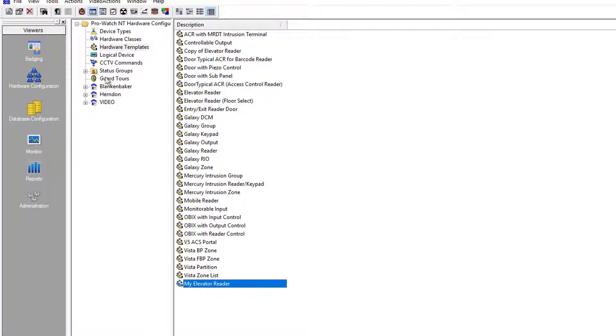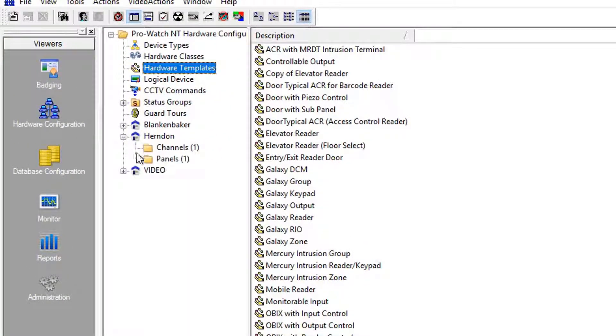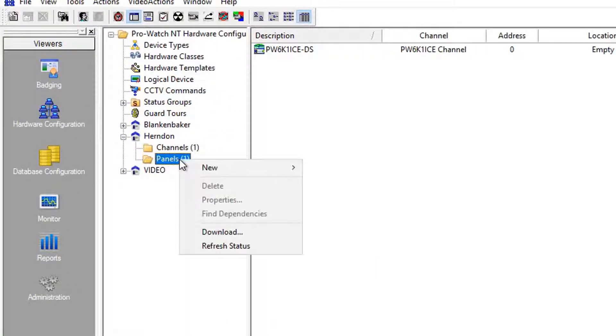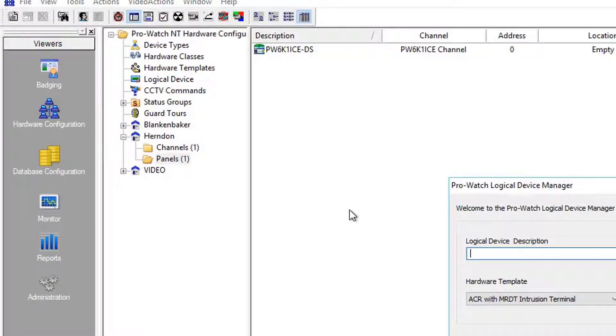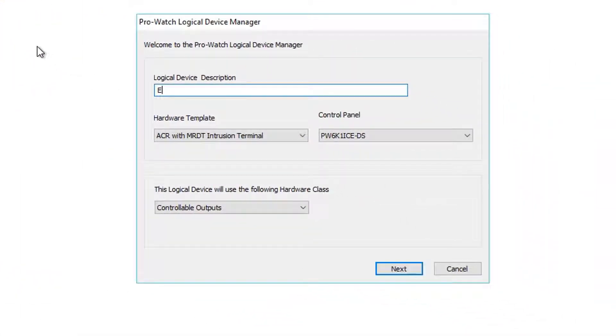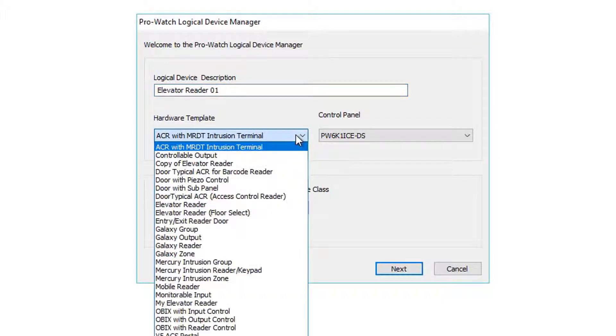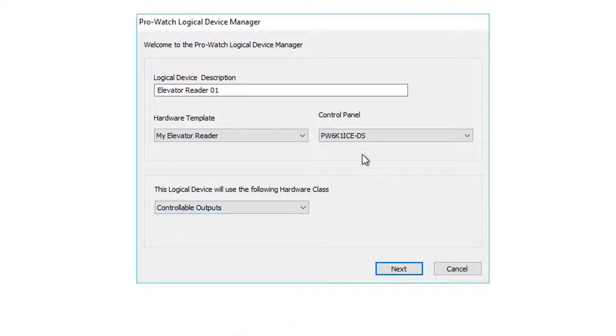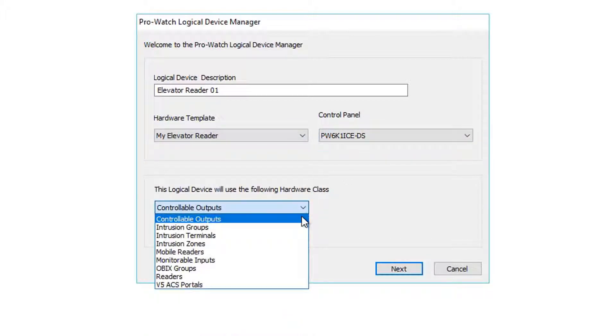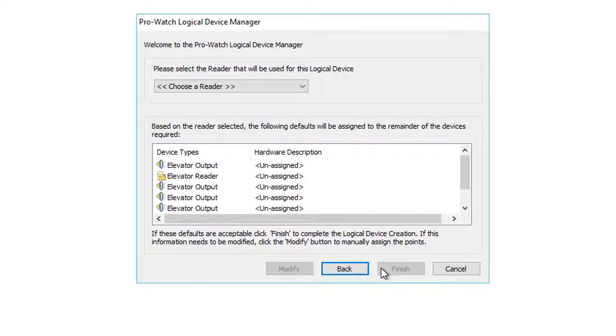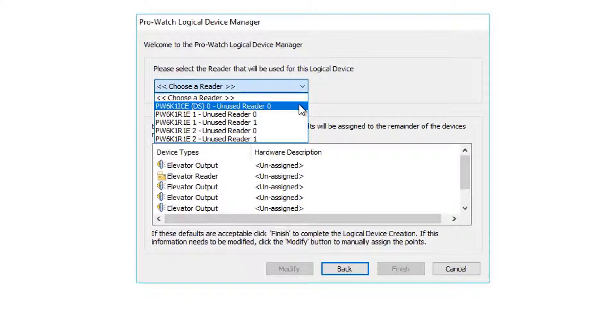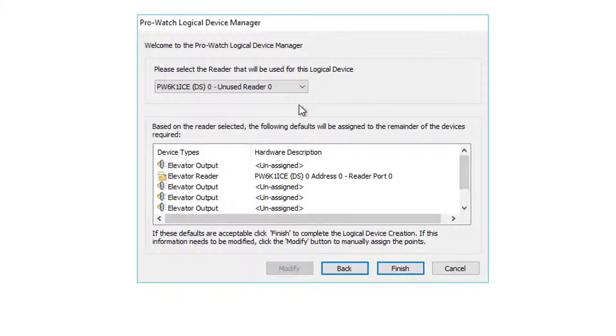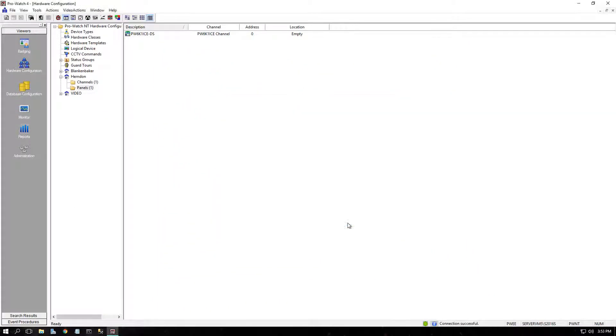Next, let's program the elevator reader. Under your site in ProWatch, perform a right-click New Logical Device. Provide the elevator reader a name. And we'll also select our hardware template as the new template created, My Elevator Reader. Select the correct controller and the hardware class, meaning the folder in which this will be assigned, Readers. Next, assign the unused reader for which your reader is hardware wired, and click Finish.